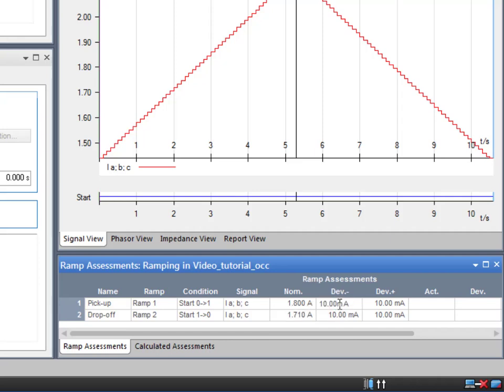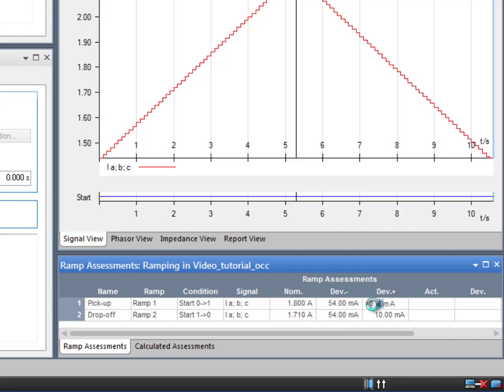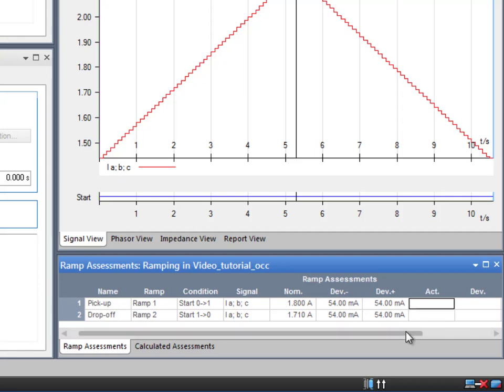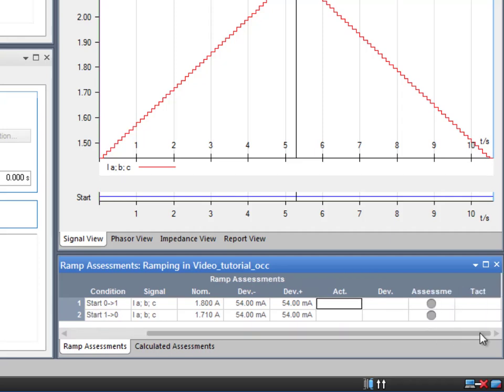The deviation contains the allowed tolerance values. As explained before, the tolerance is 3% in both directions, positive and negative. 3% of 1.8 amps makes 54 milliamps. We can keep the same value for the drop off deviation. The rest of the columns display the actual values after the test is performed.